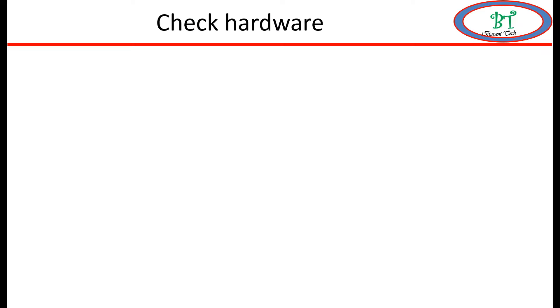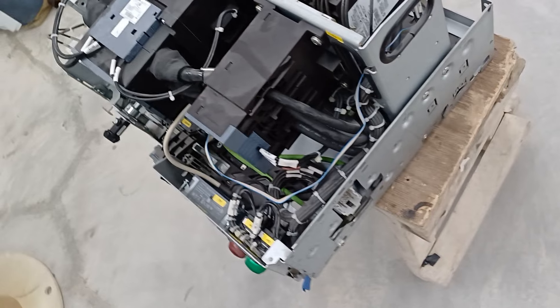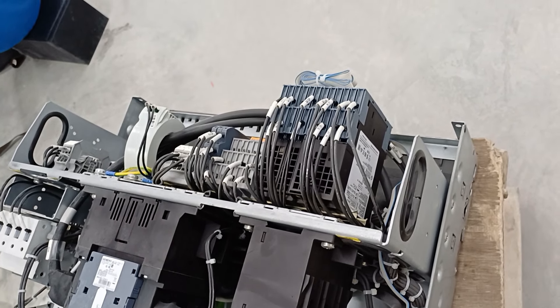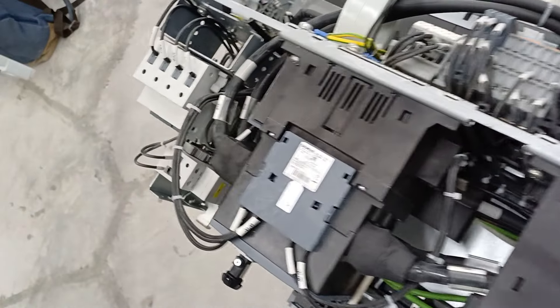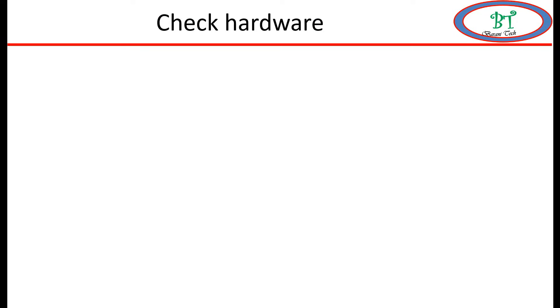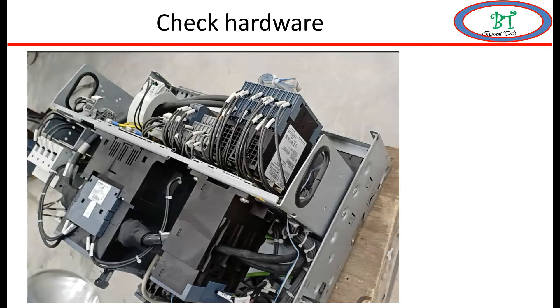For doing configuration, first we must know about the motor starting type and hardware part of the module. There are different methods for motor starting: DOL start, star-delta start, soft starter, forward-reverse start, etc. For checking the hardware part of the module, it can be seen on the schematic, but better to take the module physically and note the part number associated with the SIMOCODE relay through the communication cable. For example, I am going to do DOL start configuration.